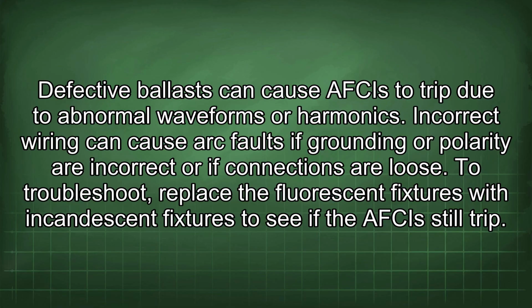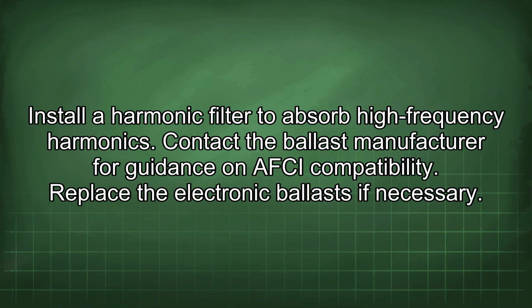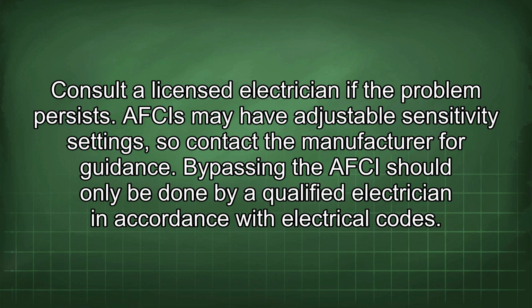To troubleshoot, replace the fluorescent fixtures with incandescent fixtures to see if the AFCIs still trip. Install a harmonic filter to absorb high-frequency harmonics. Contact the ballast manufacturer for guidance on AFCI compatibility. Replace the electronic ballast if necessary. Consult a licensed electrician if the problem persists. AFCIs may have adjustable sensitivity settings, so contact the manufacturer for guidance. Bypassing the AFCI should only be done by a qualified electrician in accordance with electrical codes.